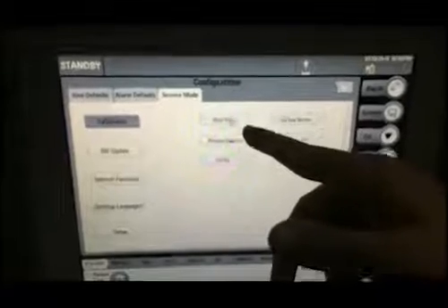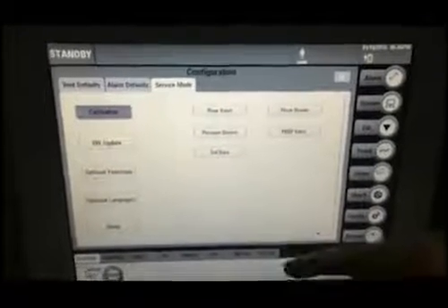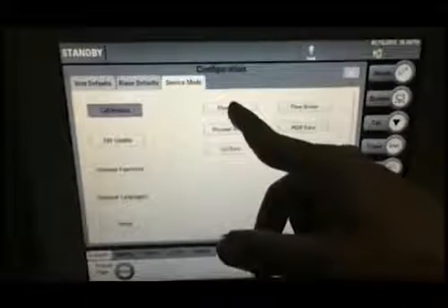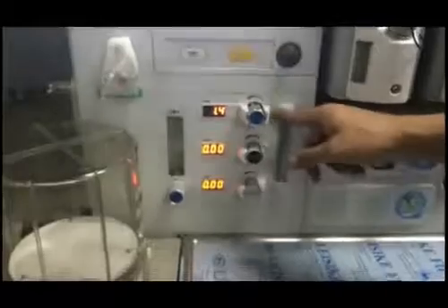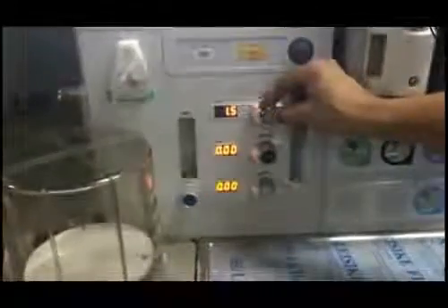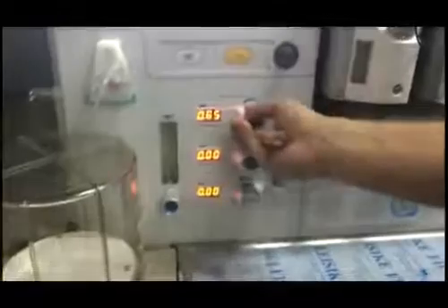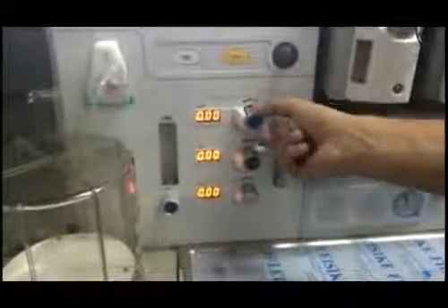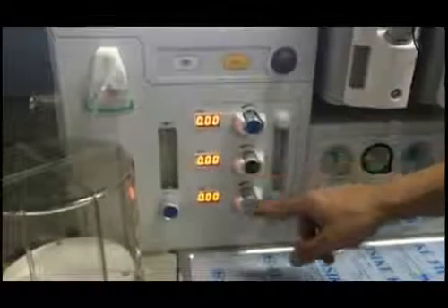Now we will perform the calibration of the flow valve. In order to perform the calibration of the flow valve, please press the flow valve button. Now please read the instructions. The first step is to set the flow meter to 0 liter per minute. There are 3 flow meters: O2 flow meter, air flow meter and N2O flow meter. We have to set them to 0. As you can see, now all the flow meters are set to 0.